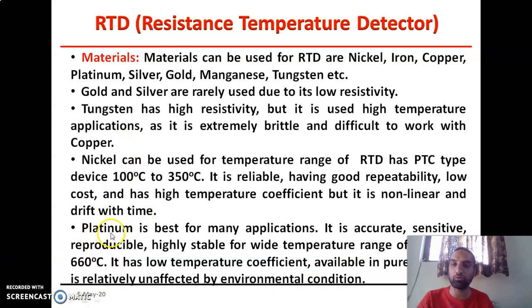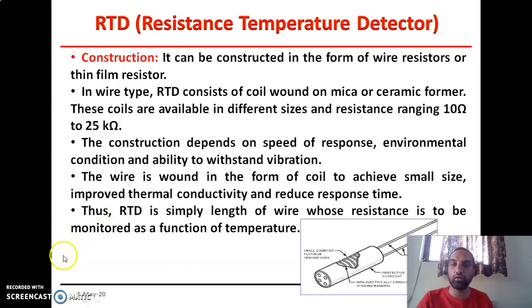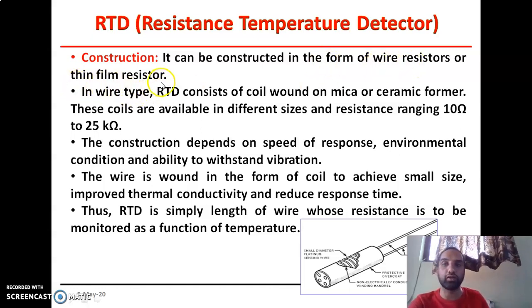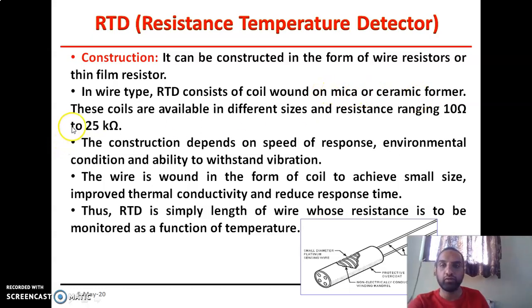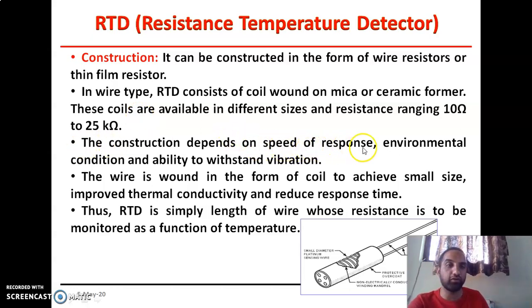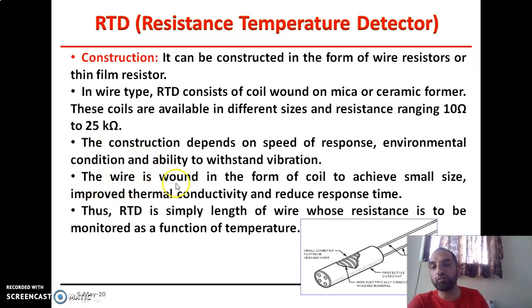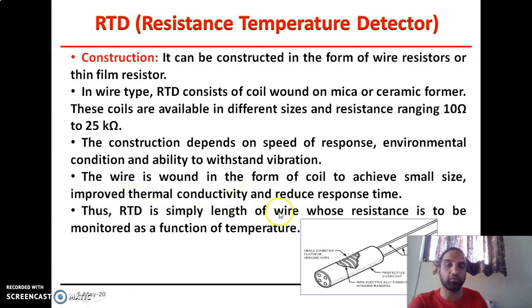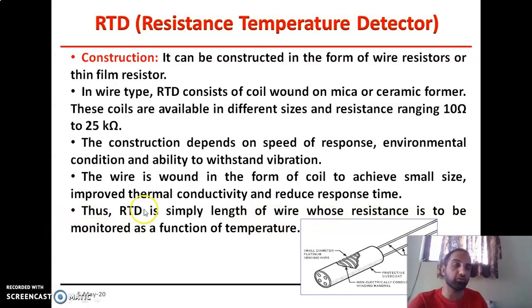RTD can be constructed in the form of a wire resistor type or thin film resistor type. In the wire type, the RTD consists of a coil wound on a mica sheet or ceramic form. The coil is available in different sizes with resistance values ranging from 10 ohms to 25 kilohms. The construction depends upon the speed of response, environmental conditions, and the ability to withstand vibration. The wire is wound in the form of a coil to achieve small size, improve conductivity, and reduce response time.